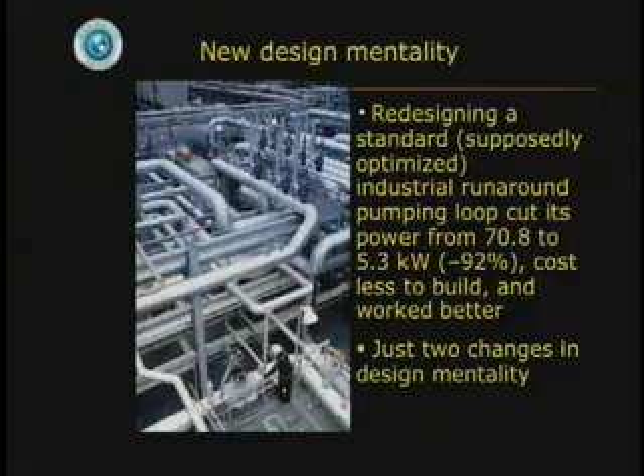But then a Dutch engineer, Jan Schillem, redesigned it to use 5.3 kilowatts, which was 92% less—some uncertainty about that number we're still nailing down, but it was a very dramatic reduction. It cost less to build and worked better in every respect, not because of any changes in the pumps, motors, process, or controls, but because of two changes in the design mentality.